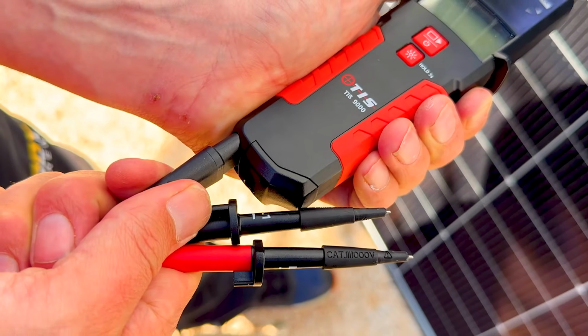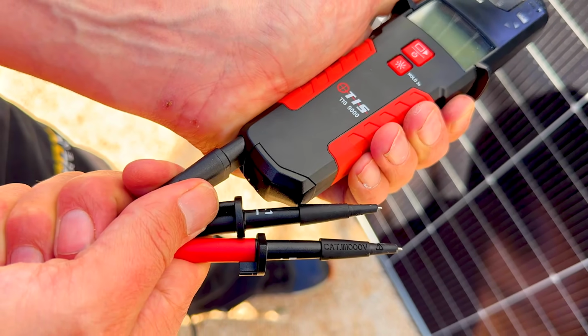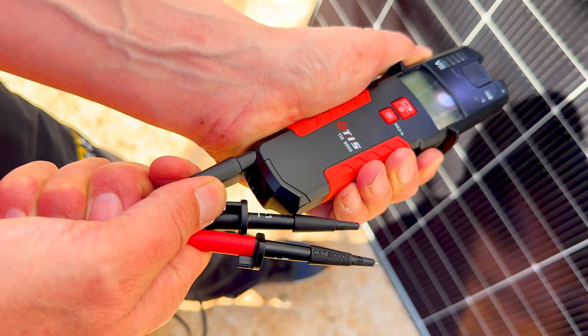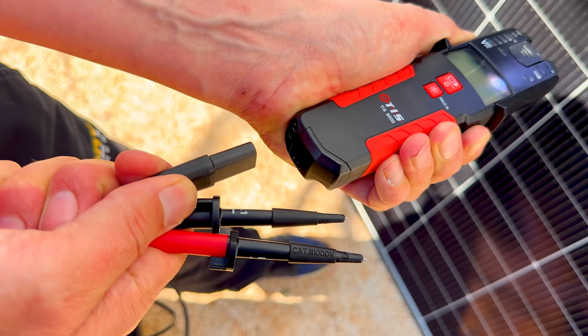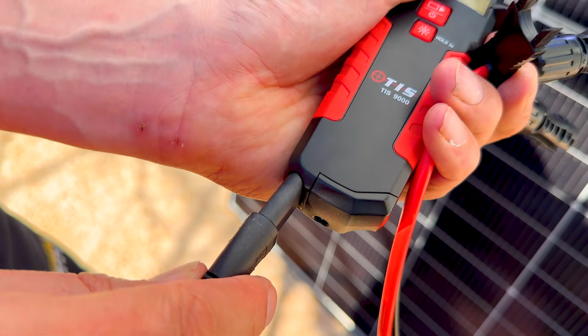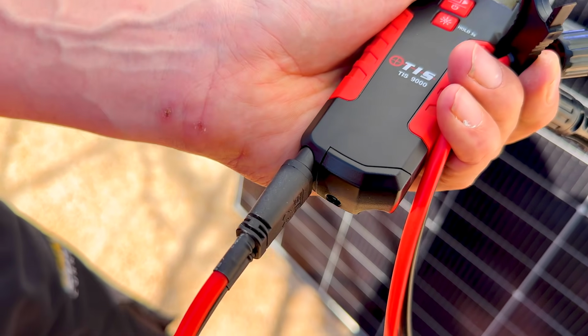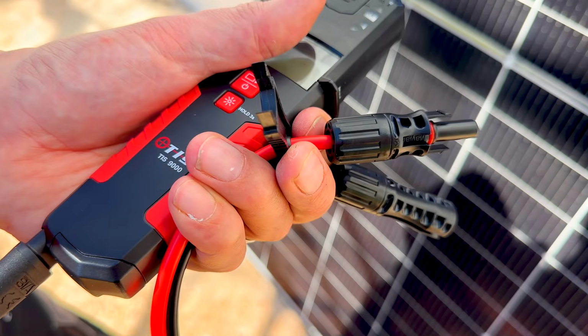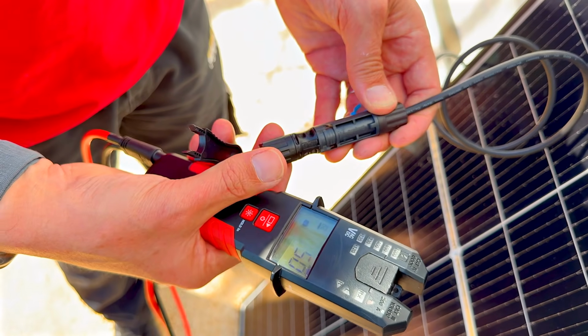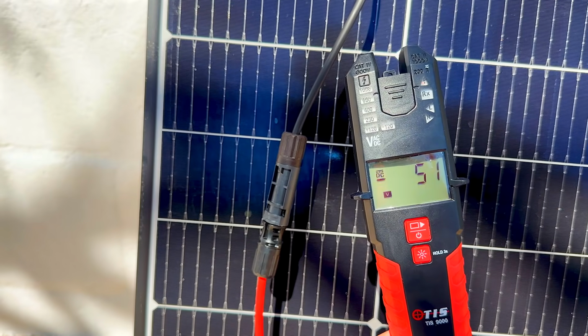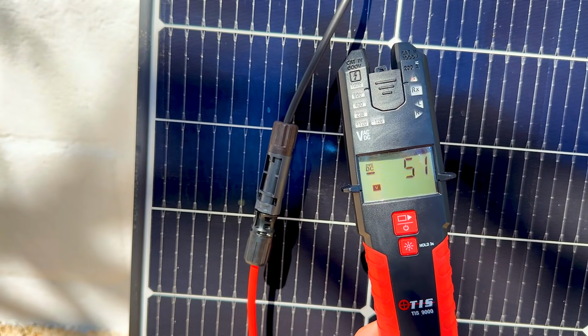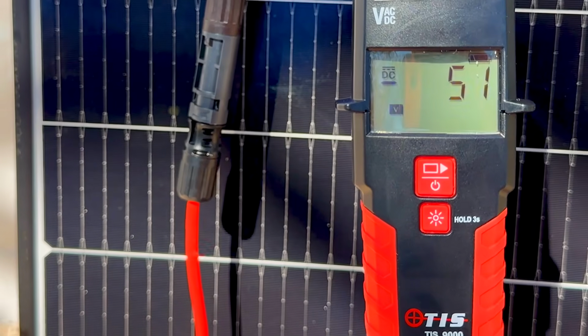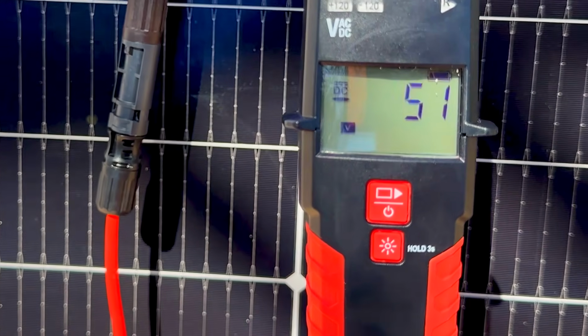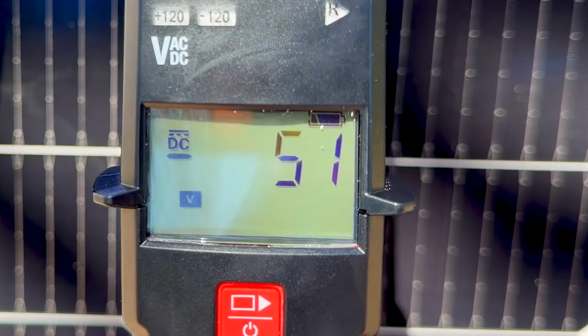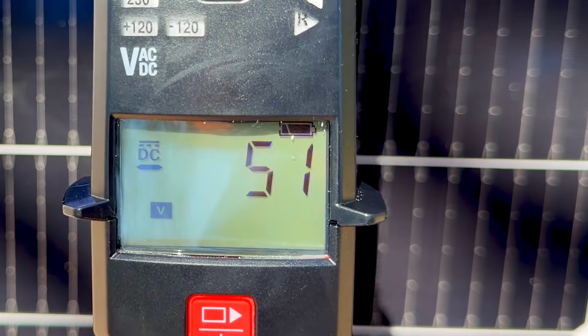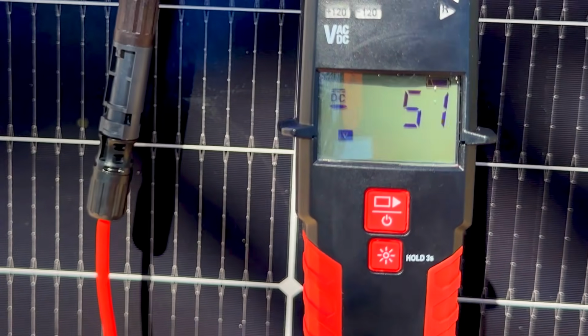One of the standout features of this unit is how easy it is to swap out the test leads. If they get damaged, you simply unplug them from the socket and replace them. No fuss, but it's not just about maintenance. This opens up a really useful feature for solar work. You can swap the standard probes for MC4 test leads and go straight onto the string. That means you can quickly measure string voltage, check you've got the correct number of panels connected, or carry out a fast polarity check. No adapters, no workarounds, just straight onto the connectors you're already using.